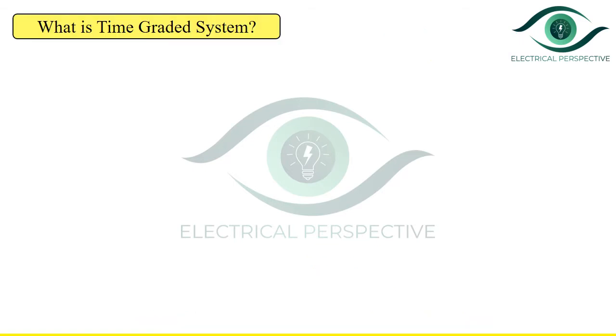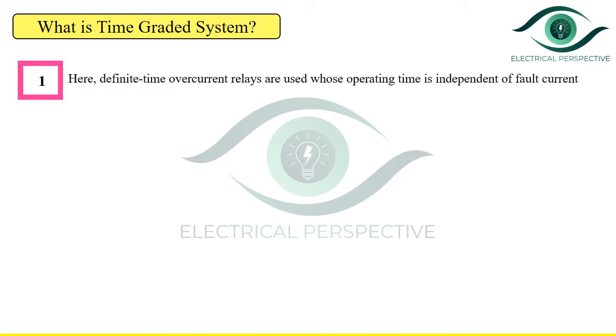What is a time graded system? It is a scheme of overcurrent protection in which time discrimination is incorporated. The time setting of the relay is so graded that in the event of a fault, the smallest possible part of the system is isolated. Here we use definite time overcurrent relays whose operating time is independent of the fault current.